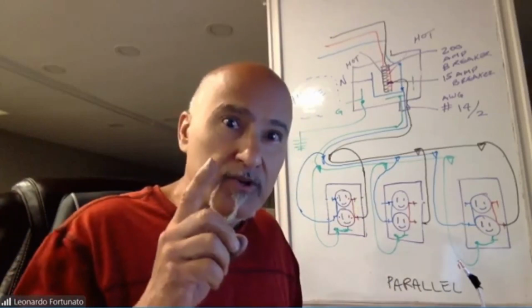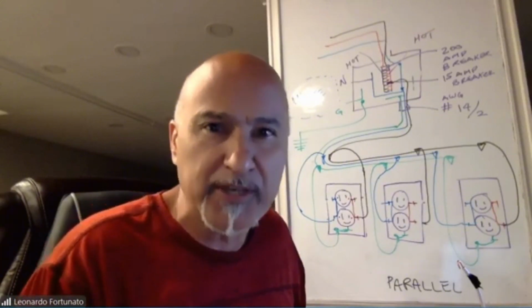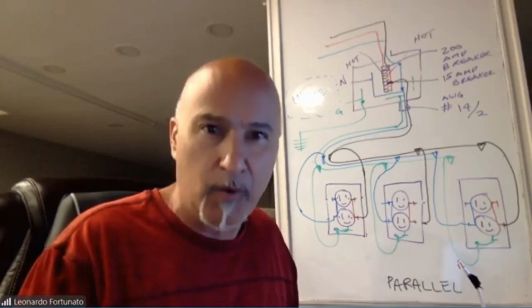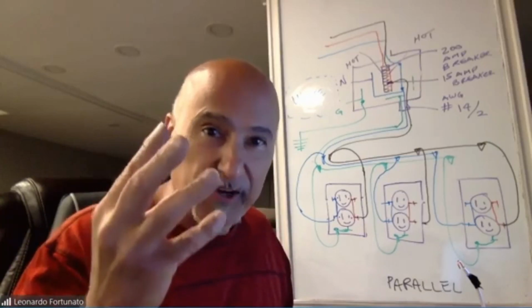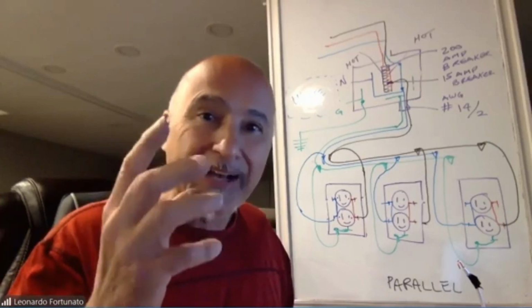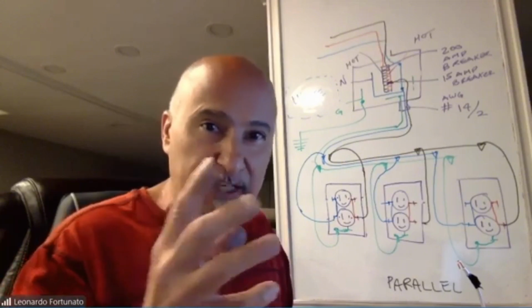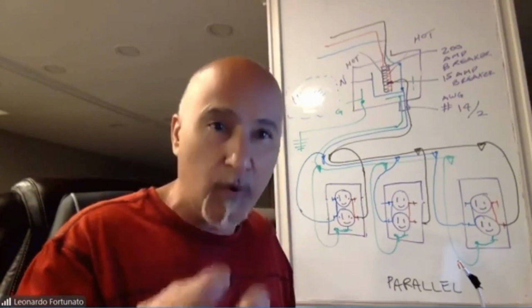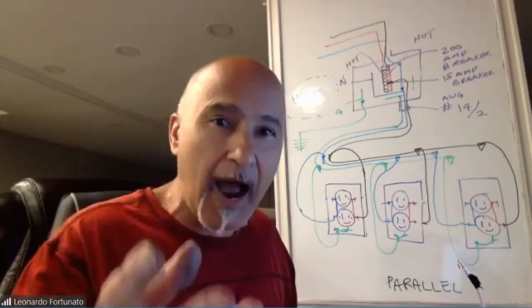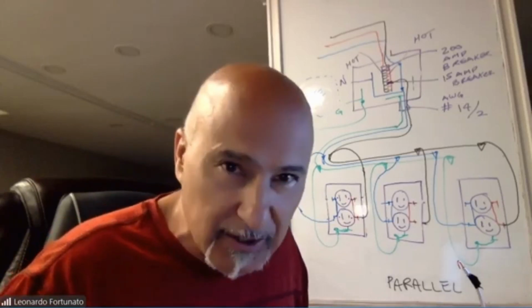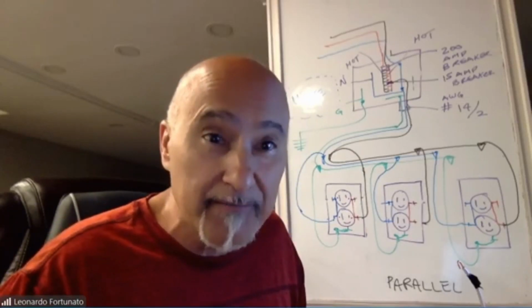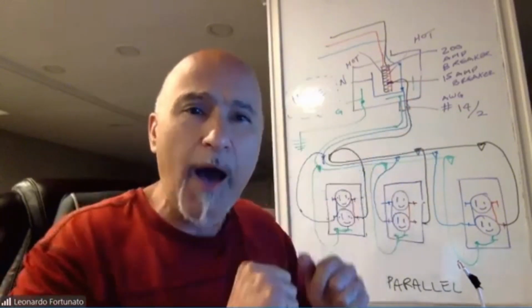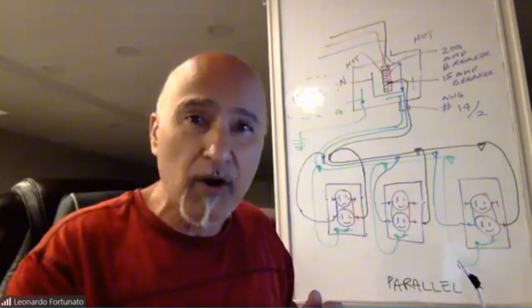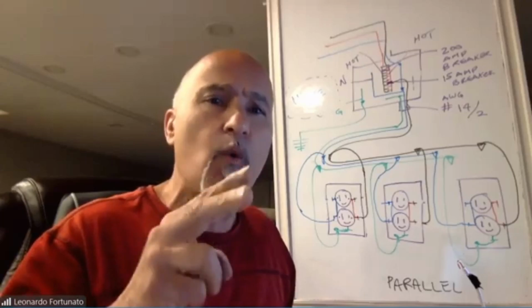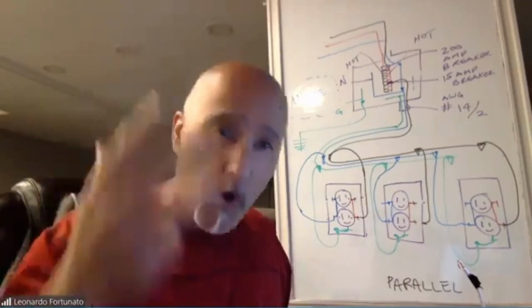But Jamal comes along and says, I'm not going to put 60-watt bulbs in my fixture, I'm going to put a 100-watt bulb. So now we have 20 fixtures, and Jamal ignored the fact that we're supposed to put 60 watts in the fixture. Now 20 times 100 is 2,000 watts. Boom, the power is going to go off, because he went 200 watts over the total capacity.